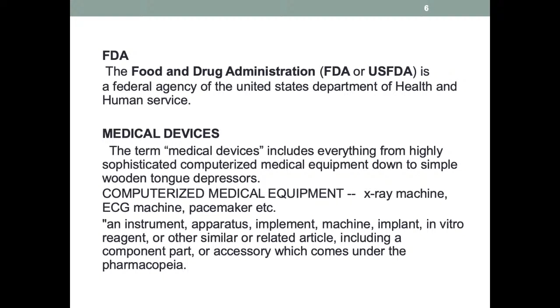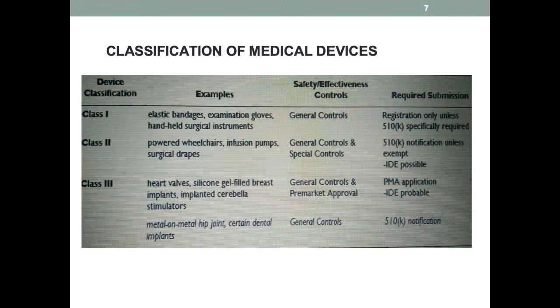So, classifications of medical devices: class 1, class 2 and class 3. Class 1 examples are elastic bandages, examination gloves, handheld surgical instruments. In class 2: powered wheelchairs, infusion pumps, surgical drapes. In class 3: heart valves, silicone gel filled breast implants, implanted cerebellar stimulators, and so on. So, device class and regulatory controls.